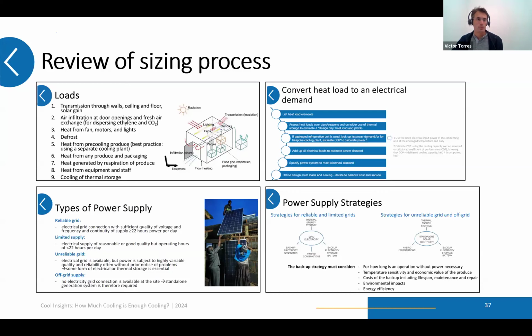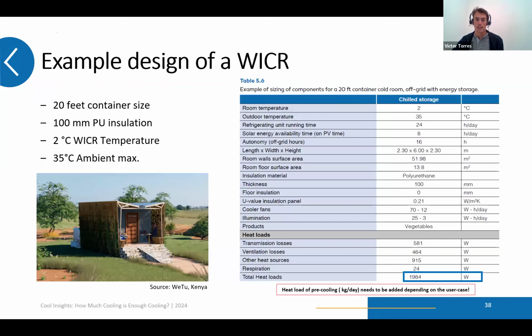Let's go to the next slide and get into more detail. As mentioned, section 4 of the guide has all the equations for calculating cooling demand, and section 5 has examples, like the one in table 5.6, showing a typical 20-foot container-sized walk-in cold room with 100 millimeter polyurethane insulation, typical sandwich panels.